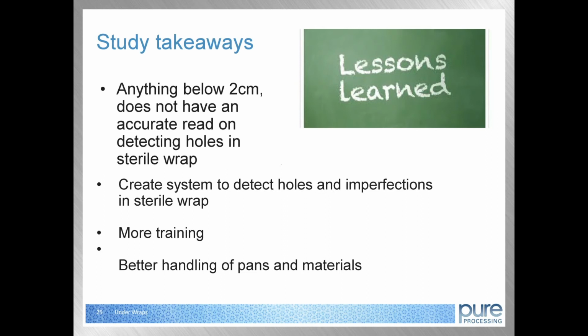One thing we also need to do is handle the pans better. Once the pan is sterile, it goes from sterile processing and gets sterilized, goes from the autoclave rack and then to the storage unit and the storage shelf. When we take it off of the shelf, we need to use something to protect the bottom of it so that once it goes on the case cart, it does not have a chance of rubbing up against anything sharp. That's something we can do to prevent holes from happening. And then once it goes up to the OR, we've got to be able to do the same.